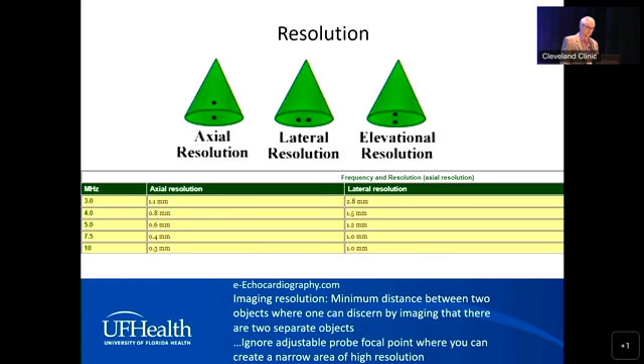And ignore this for now, that would be 3D issues. But this is a resolution across the screen, and lateral resolution is typically always less than axial resolution. Here with a 10 megahertz probe, our lateral resolution is such that we cannot distinguish two objects when they are close together, less than 1 millimeter apart. It just looks like a blur, and I'll show you an example of that. So there are issues with the resolution of the machine we use.